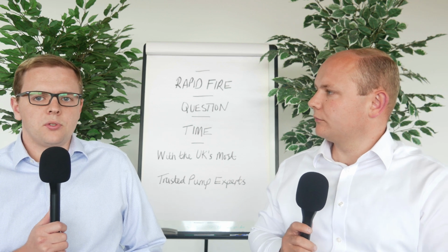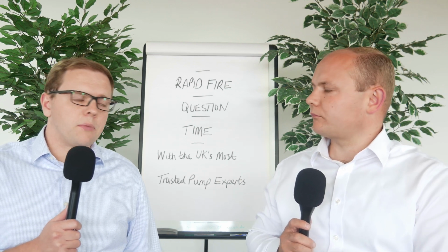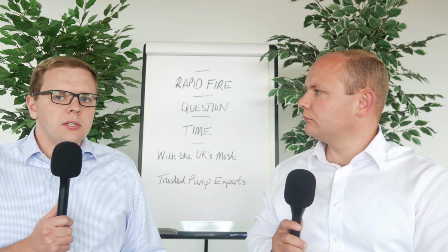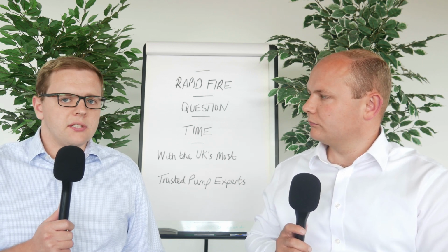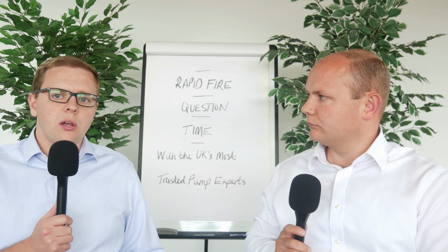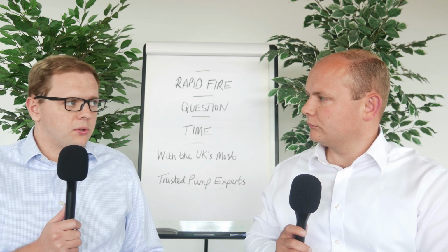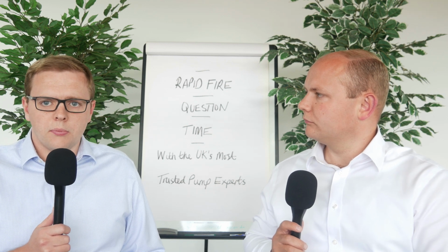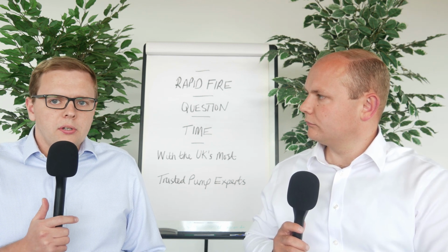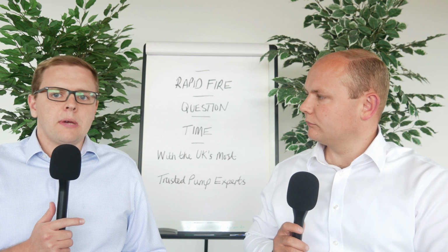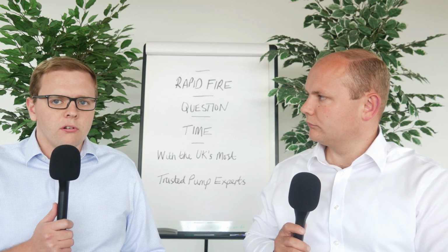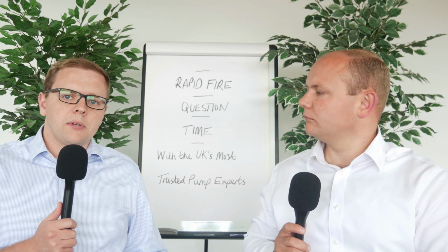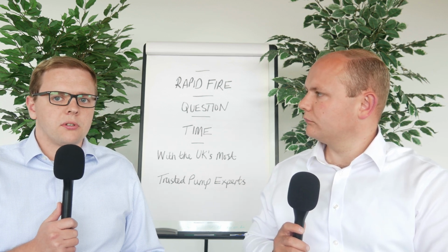Yep. So duty assist is great where you may have multiple flow rates, and we can calculate the types of pumps you require in the system to ensure that you're hitting both those lower flow rates for the smaller storms and the higher flow rates when you do get that 1 in 100 year storm. Or on other schemes there may be other requirements for different flow rates, but we can use a duty assist system to calculate and get the best pumping solution for the site.